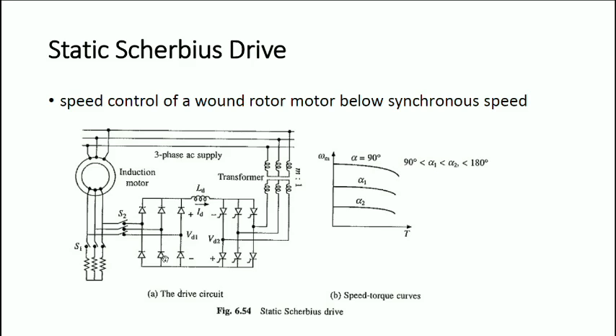Before going further, let me compare with rotor resistance control. In rotor resistance control, the whole power is lost in the resistance. But here, the power on the rotor side is fed back to the input supply, so the total power drawn is reduced. That means the overall efficiency of the drive is increased.